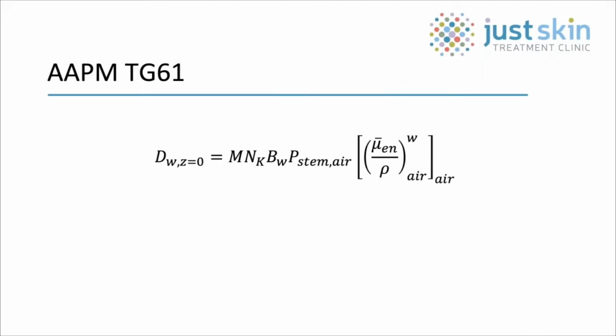Australians and Americans will be familiar with this formula from TG61 to calculate the dose to water at the surface of a phantom. This can seem like the scariest part, but I hope you'll believe me when I say that it's very simple. M is the electrometer reading corrected for temperature and pressure, as with most radiotherapy measurements. NK is the calibration factor taken from the ion chamber's calibration certificate. This should be corrected if the measurement distance differs from the calibration distance, which will be explained in the next slide. When interpolating between NK values on the calibration certificate, be sure to use the HVL obtained using the correct SSD. In my case, this was 30 centimeters.